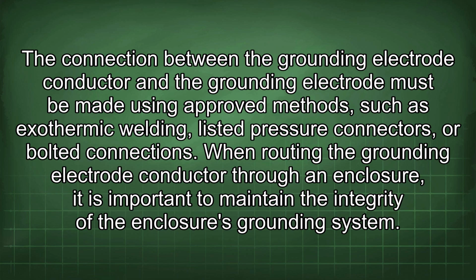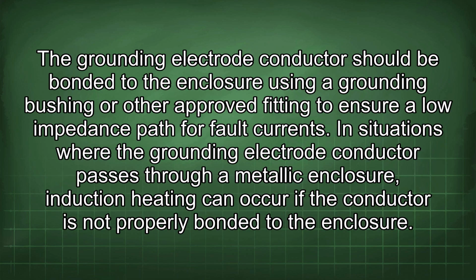When routing the grounding electrode conductor through an enclosure, it is important to maintain the integrity of the enclosure's grounding system. The grounding electrode conductor should be bonded to the enclosure using a grounding bushing or other approved fitting to ensure a low impedance path for fault currents. In situations where the grounding electrode conductor passes through a metallic enclosure, induction heating can occur if the conductor is not properly bonded to the enclosure.